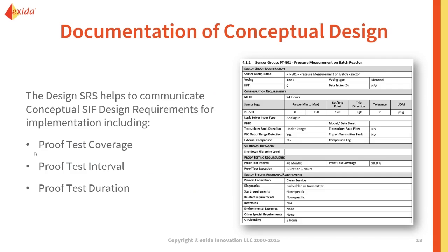So this is going to communicate the finalized proof test coverage, proof test interval, and proof test duration for your proof test strategy when it comes to each of your SIFs. A lot of the information in the design SRS is pulled straight from SIL Verify and your inputs there, but it does allow you to include more device-specific requirements and more maintenance information now that you know exactly what your SIF is going to be.